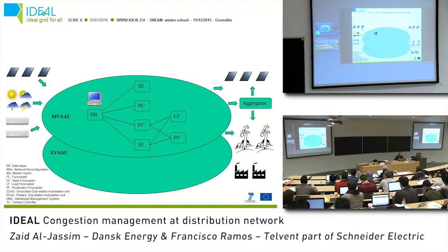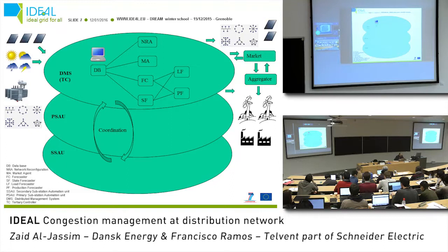The same, basically, as the power control at the low voltage level, it also controls if there is any congestion. It tries to solve this congestion by directly controlling some of the distributed energy resources at the medium voltage level, or by using an aggregator. At the control center level, we also have the DMS, or what we call the tertiary controller. It is basically also a PC where we have a database and another set of algorithms. Here we also have a state forecaster, basically the same algorithms as on the two other level controllers, but also a network reconfiguration algorithm and a market agent algorithm.